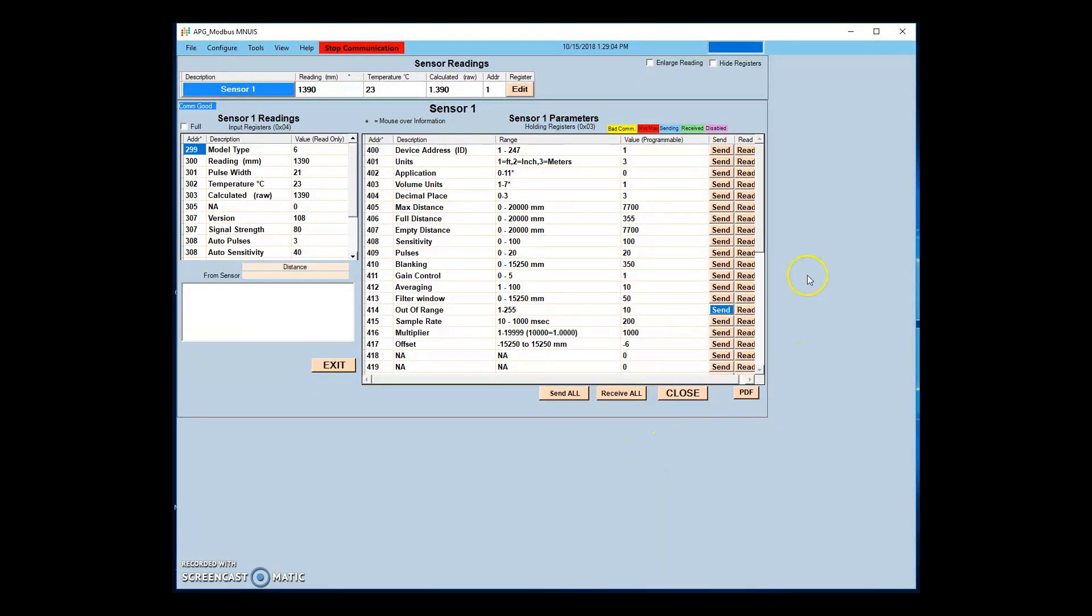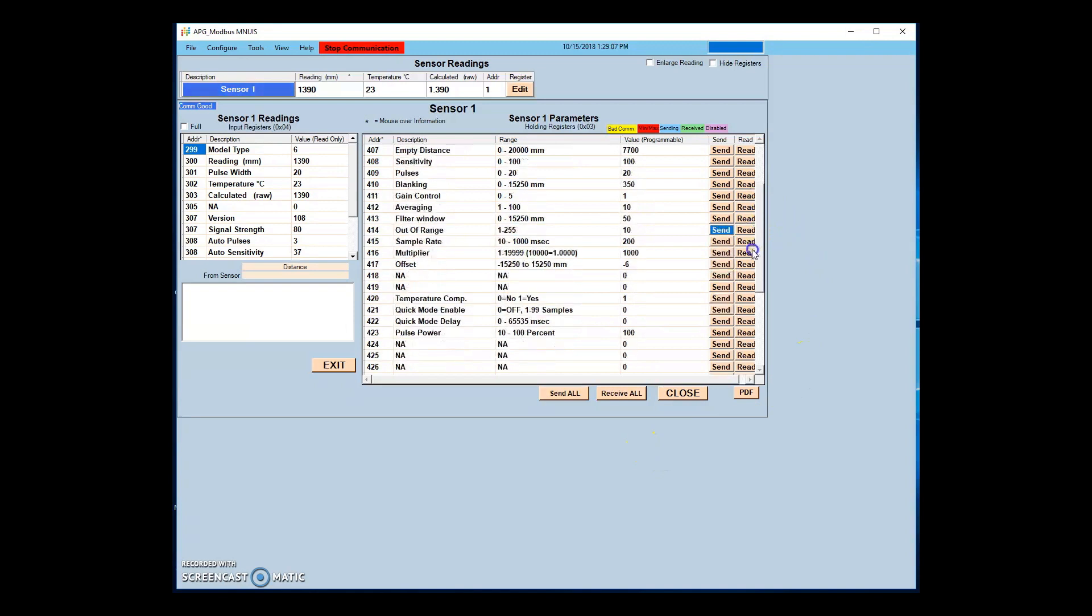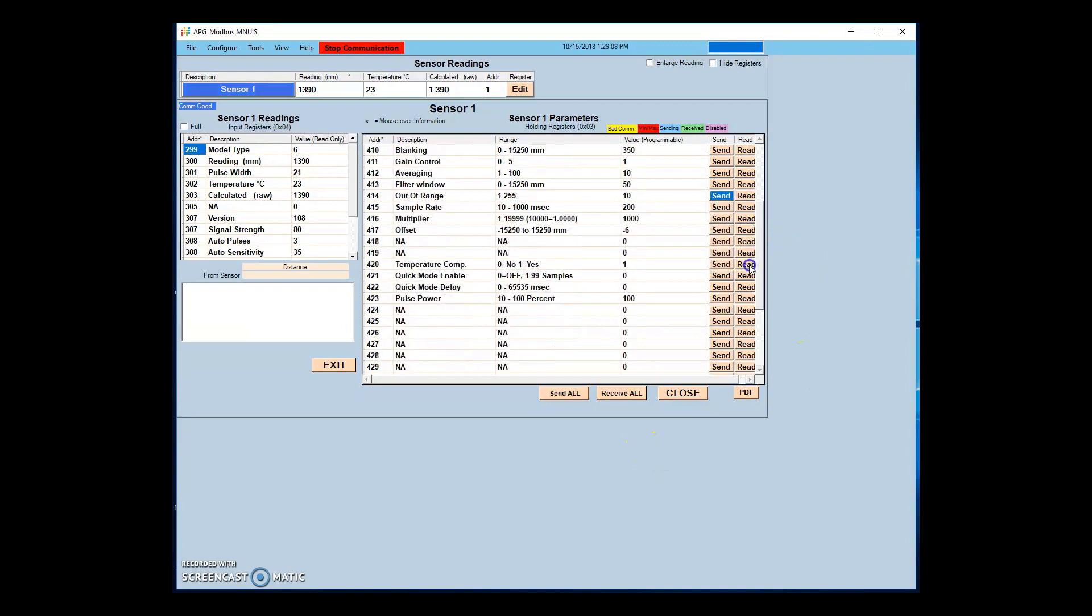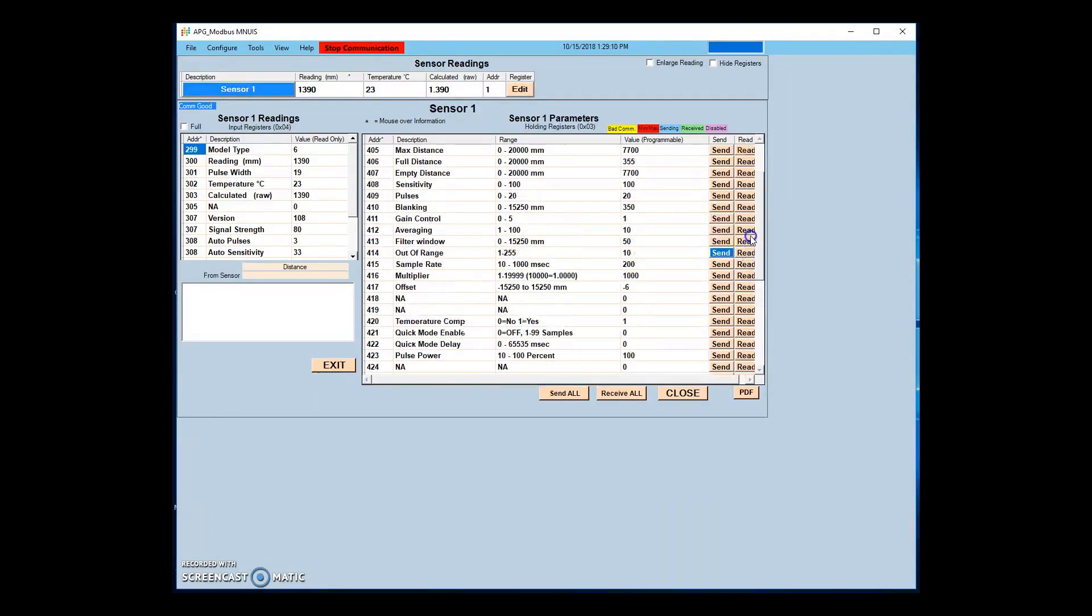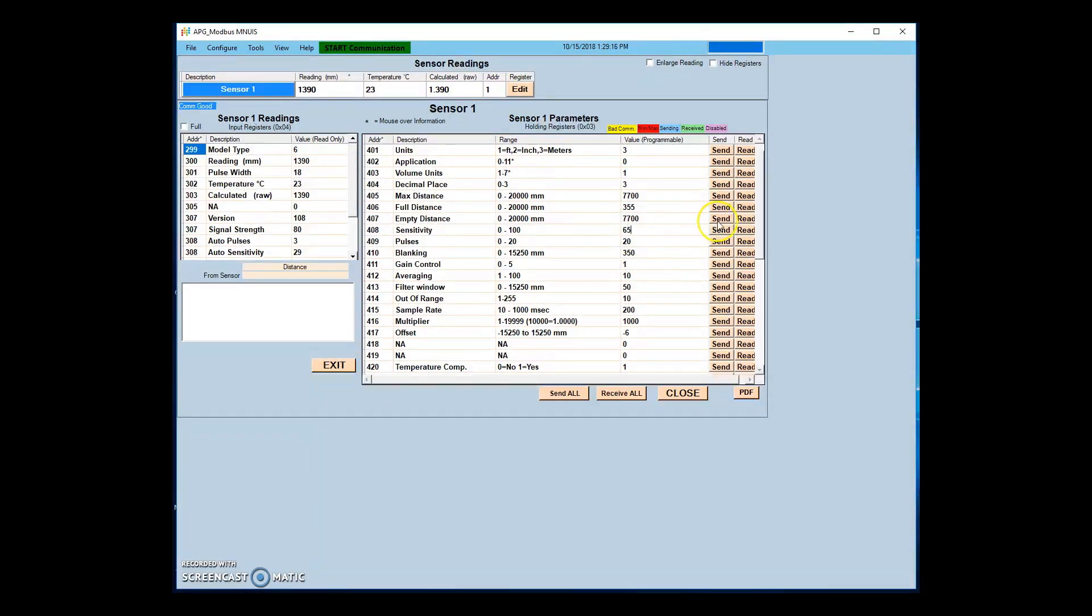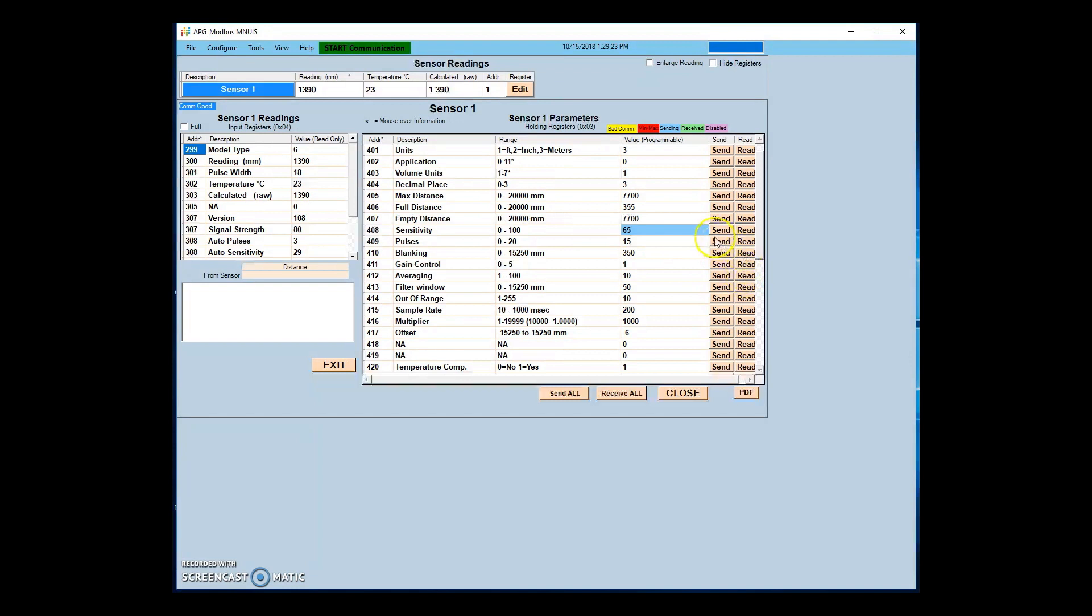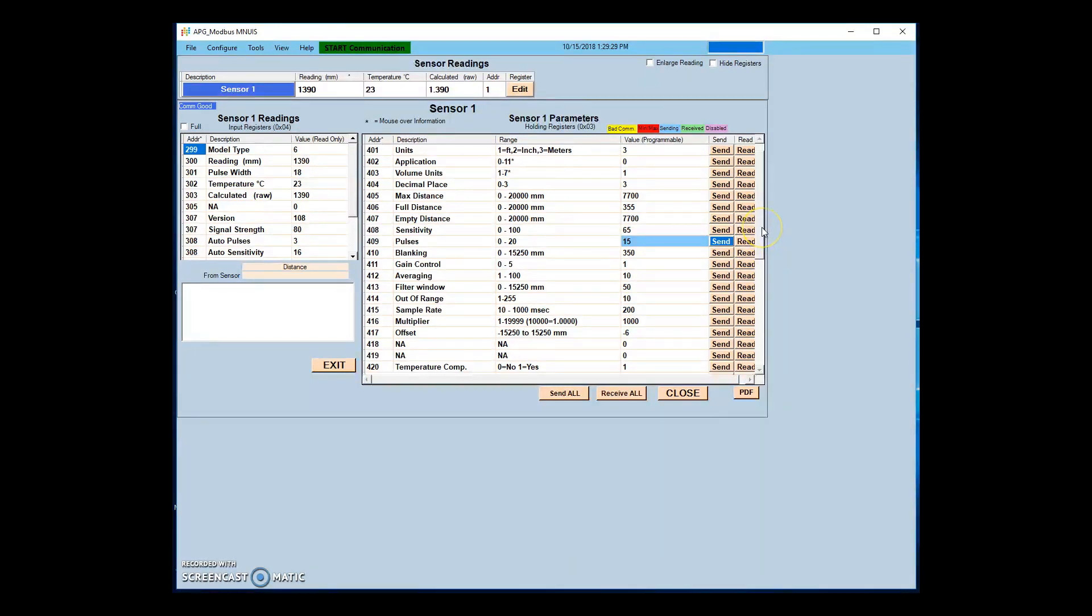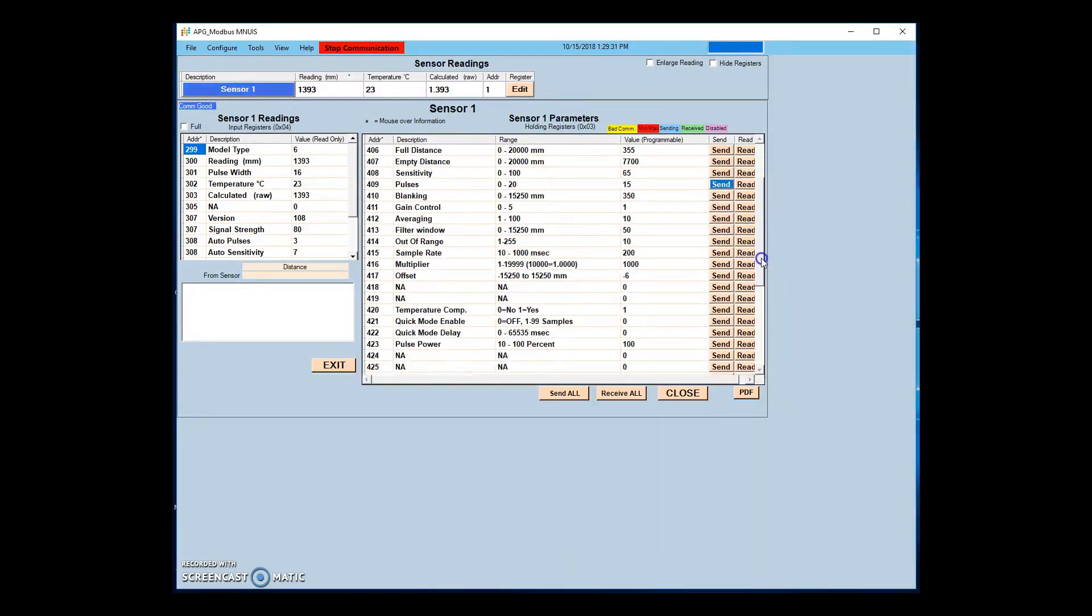To use a sensor in quick mode, it is important to first make sure that all sensor settings have been optimized for your application. This includes adjusting blanking and other distance settings to match the environment. Sensitivity and pulses should be adjusted to the lowest setting that can still read the full expected range of the sensor in all expected environmental conditions.